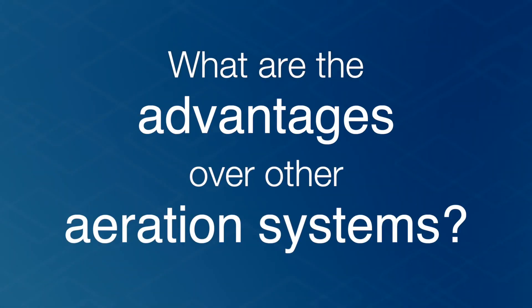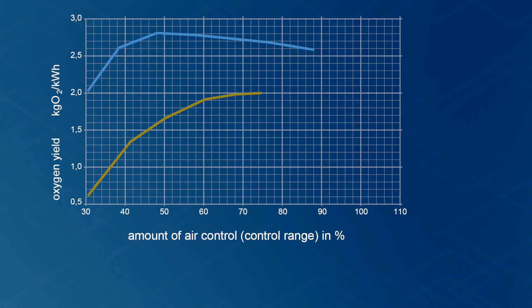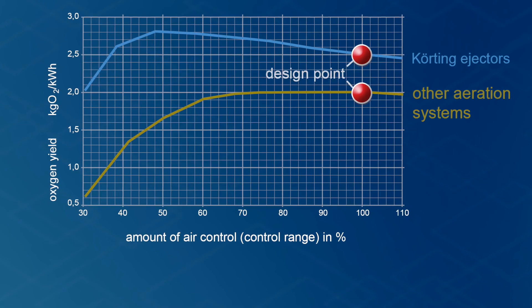The intensive flow towards the tank floor helps to avoid deposits and the oxygen supply is easy to control. When the airflow is lower, the ejector reduces discharge pressure on the roots blower and therefore its power consumption. Oxygen efficiency rises at the same time, resulting in a constantly high level of oxygen transfer across the whole control range. This is a major benefit compared to other aeration systems.